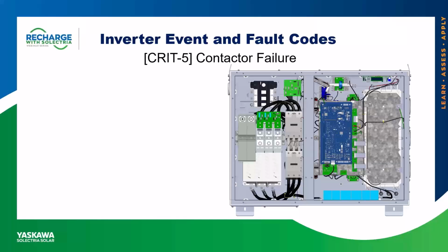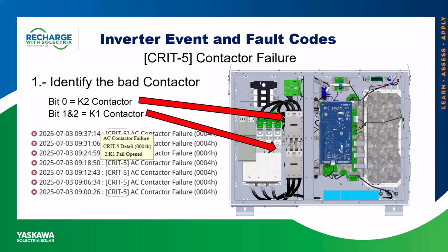Crit 5. As its name says, it could be related to a contactor failure. First, we need to identify, again, if we go to the event and fault logs and we hover over the fault code, this will tell us specifically which contactor it's referring to. So, in this picture, it says that the K1 failed open, so the issue would be with the bottom contactor. If you look at the picture, every time you call in and we say, can you check the K2 contactor, we're always referring to the top one. When we say check the K1 contactor, we're referring to the bottom one.